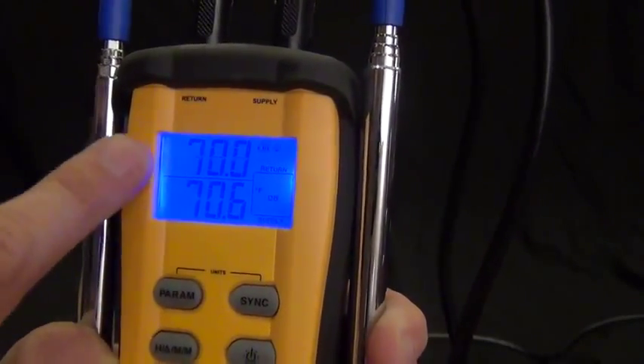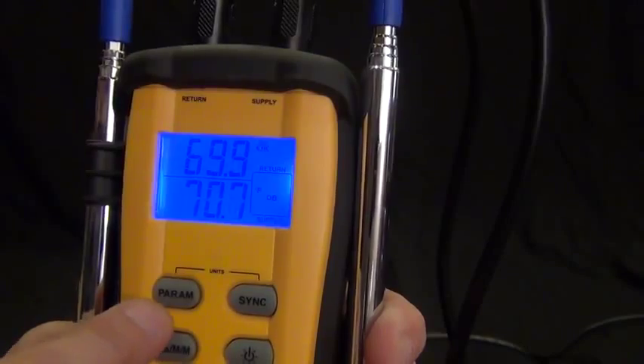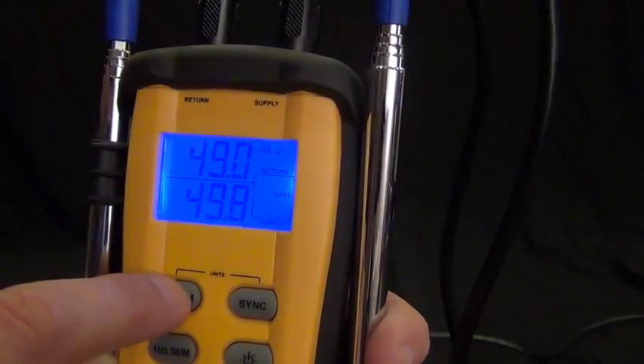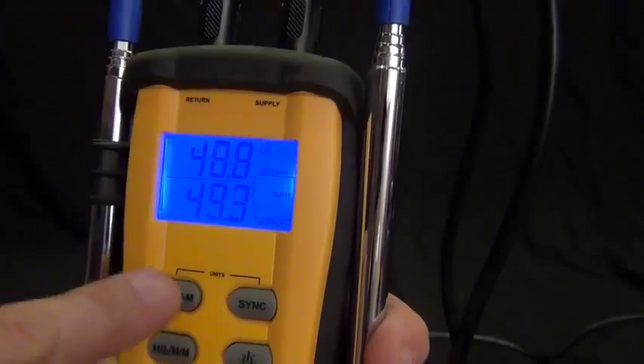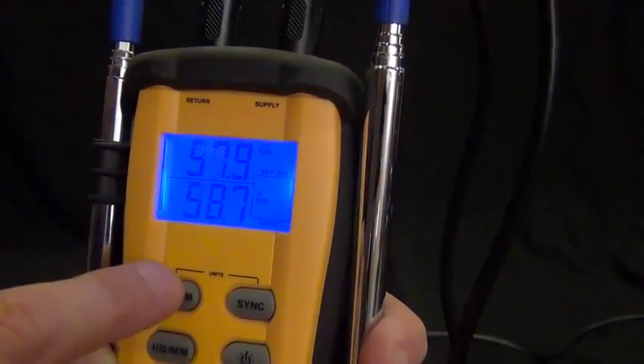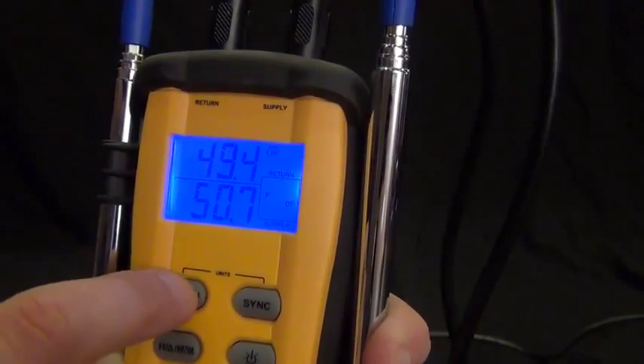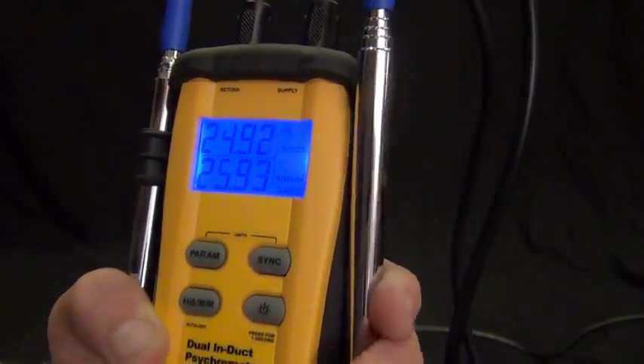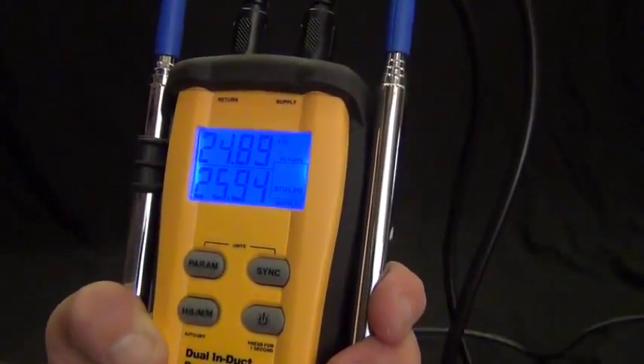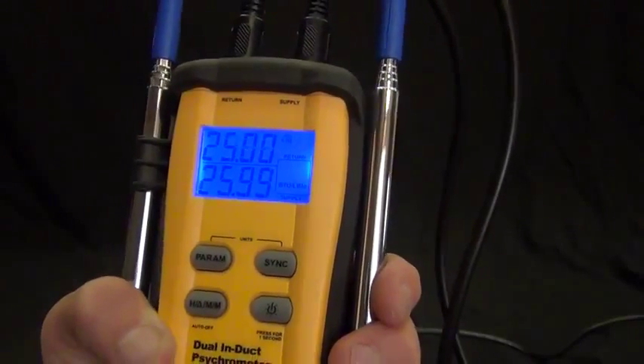And then to check out the different parameters I just press the parameter button. So I got dry bulb, relative humidity. Basically, those two measurements are used to calculate wet bulb and dew point as well as BTU per pound, which is basically your enthalpy on either side of the evaporator coil.